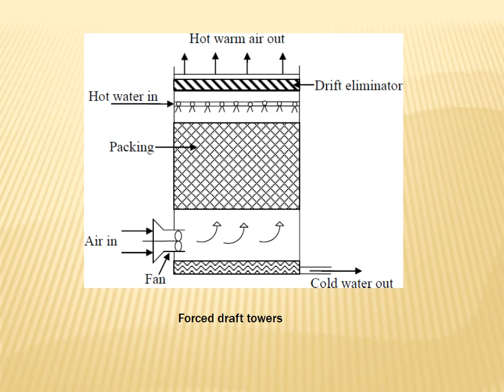When they meet each other, the water transfers the heat to the air, and it passes through the drift eliminator, where the water droplets are separated from the air, and only the warm air is passed to the atmosphere. At the bottom, the cold water is collected. The packing material is used to increase the heat transfer rate from the water to the air.